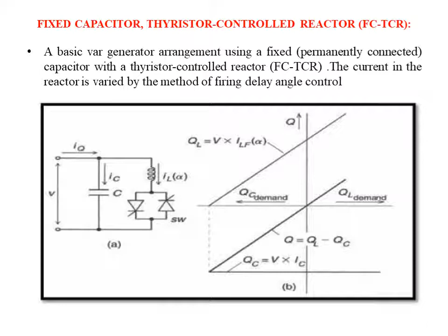The fixed capacitor in practice is usually substituted fully or partially by a filter network. So this capacitor acts as a filter, and we know that this filter is used for eliminating the harmonics which are generated by back-to-back connected thyristors. So the fixed capacitor in practice is usually substituted fully or partially by a filter network that has necessary capacitive impedance at the fundamental frequency to generate the reactive power required, but it provides low impedance at selected frequency to shunt the dominant harmonic produced by TCR.